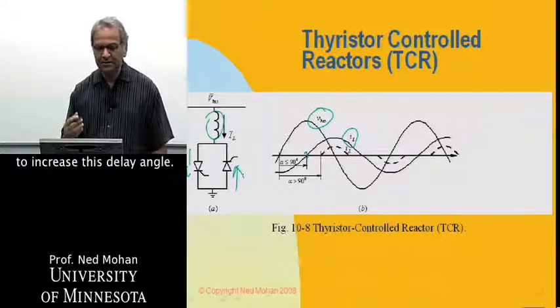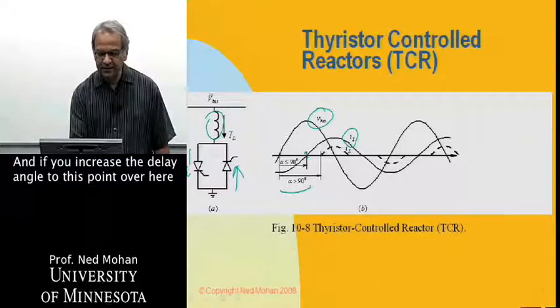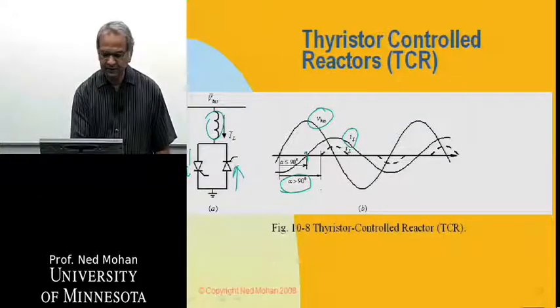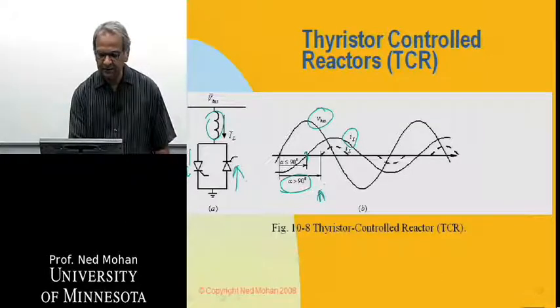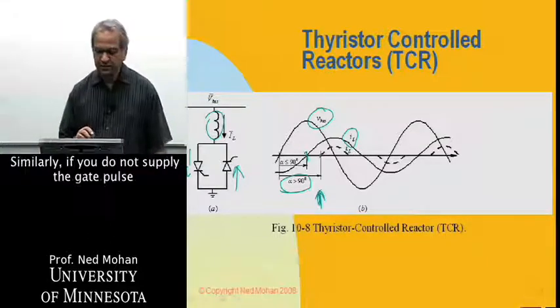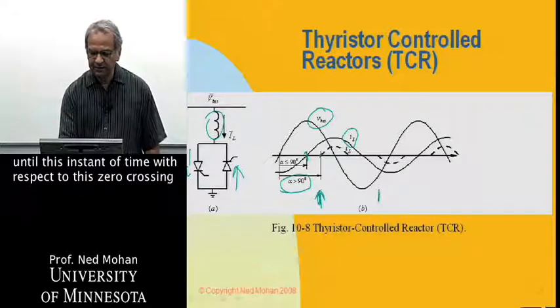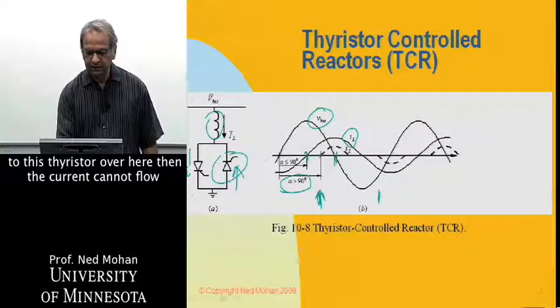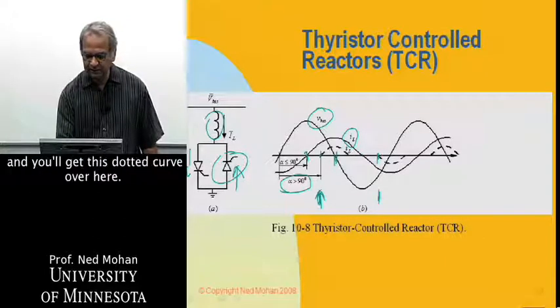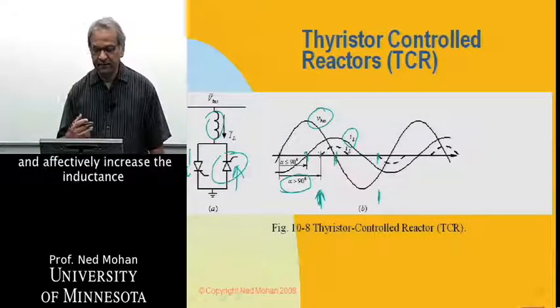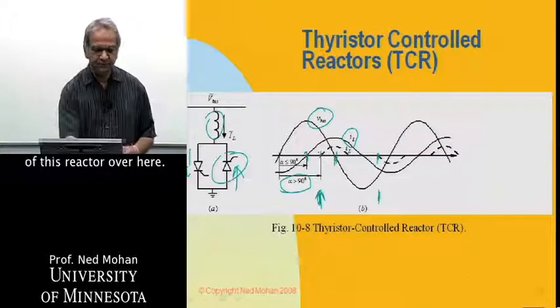With thyristors, we have the capability to increase the delay angle. If we increase the delay angle beyond a certain point and do not apply a gate pulse to a given thyristor until a later time, the current cannot begin to flow until that time. The resulting current waveform is shown by the dotted curve. By increasing this delay angle, we can make the current smaller and effectively increase the inductance of this reactor, giving us control over the reactive power — and in this case, the current is lagging behind the voltage.